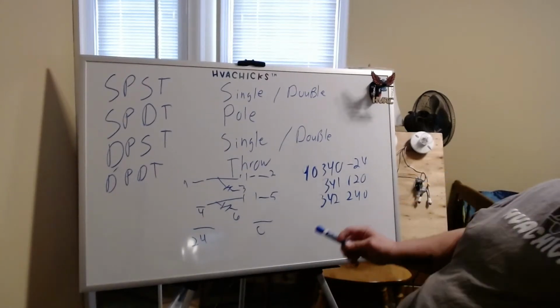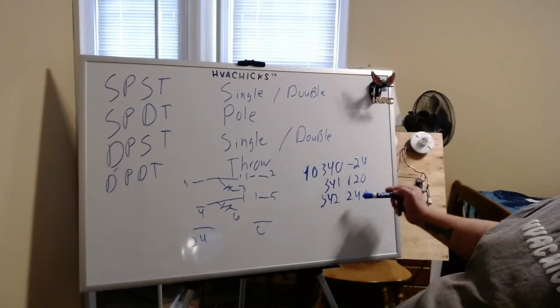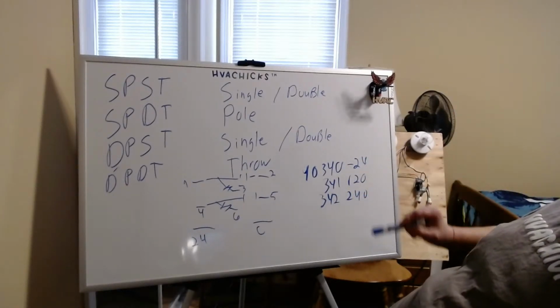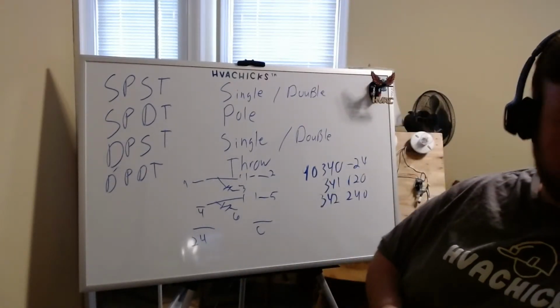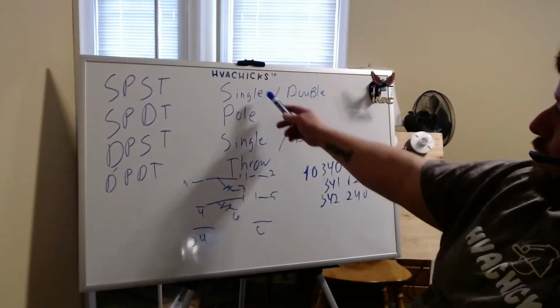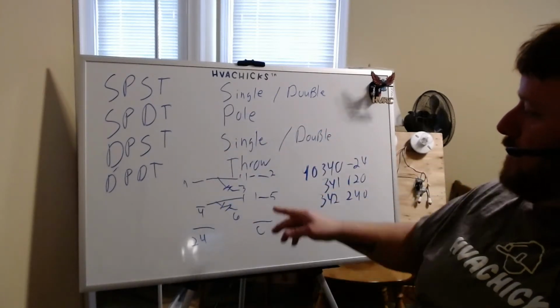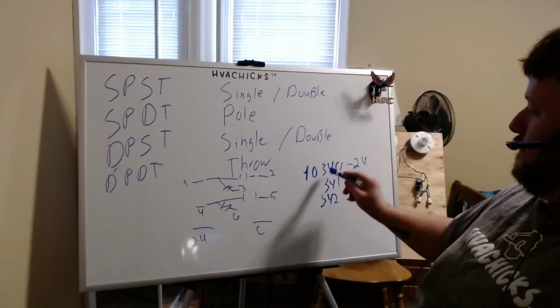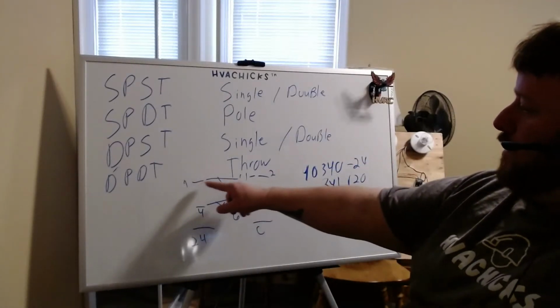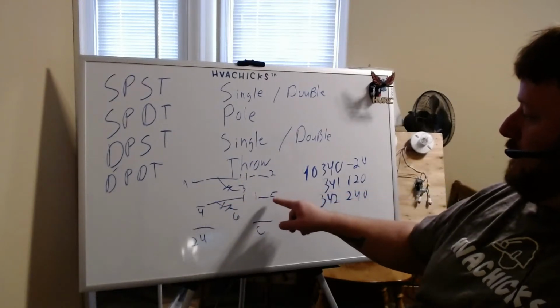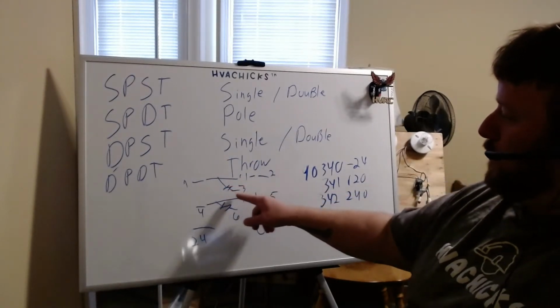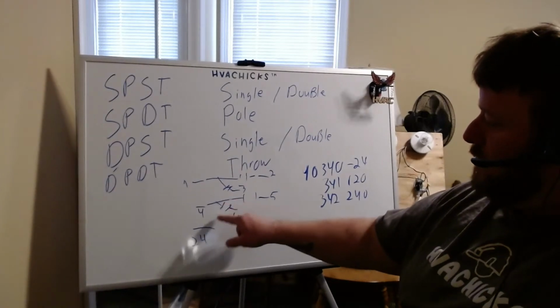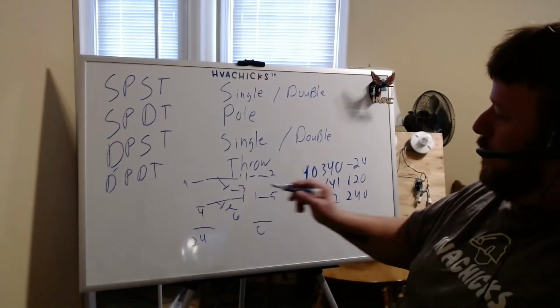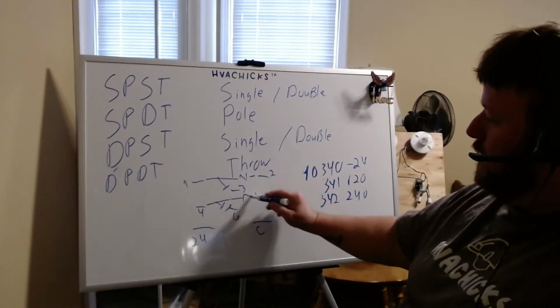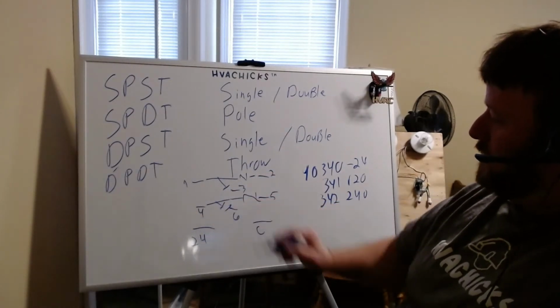So, with that being said, it depends on your relay, depends on your coil voltage. I have a 120 over there, which I showed last week, but we'll go over it still because it's all part of the controls and everything else we have to deal with. So, these acronyms apply to this. Now, there are other relays that have different numbers that look the same, where 1 to 2 is normally open, 4 to 5 is normally open, 4 to 6 is normally closed, and 1 to 3 is normally closed. When power gets energized, 1 to 2 get closed, 4 to 5 get closed, 1 to 3 opens, and 4 to 6 opens.